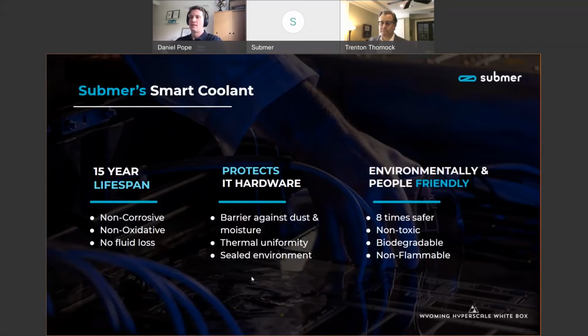Through accelerated testing, we've had installations already running for nearly 5 years with this fluid, and we have no reason to think they won't make it to the 15-year lifespan. Accelerated testing has proven these fluids are capable of lasting multiple iterations of IT hardware, and most probably the full lifespan of the data center as well. The fluids are non-corrosive, they don't oxidate, and most interestingly, there's a 0% evaporation rate, so there's no topping up of these fluids. They're designed as a non-consumable product, so it's really just part of the cooling infrastructure built into the immersion tanks.